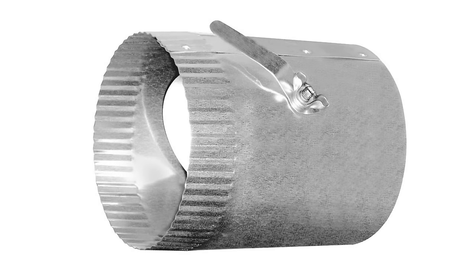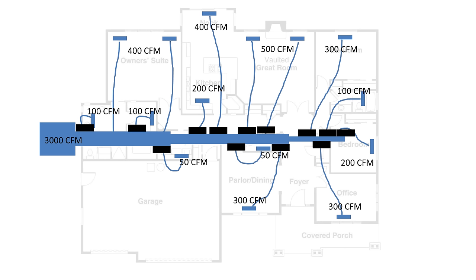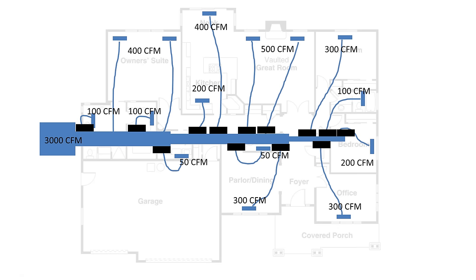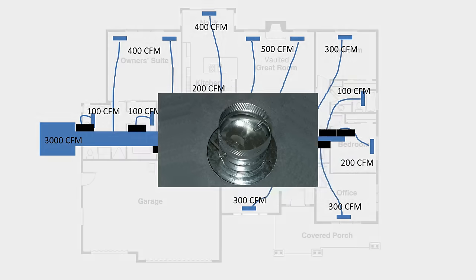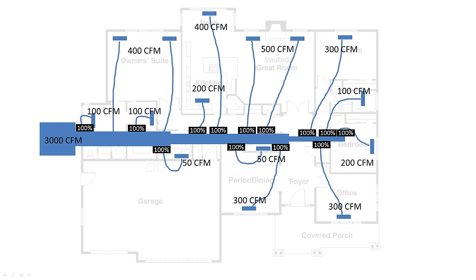Over the next few minutes I want to show you how to fix a typical forced air system the right way. When an engineer designs a house, they compute the heat load for each room and then the required airflow to be supplied to each room, then design an appropriate duct system. They can't get it exact, so they put little dampers — these little black boxes — at the intersection of the trunk duct and the branch ducts. But during installation, nobody goes back and sets these dampers to achieve the correct airflow to each room.